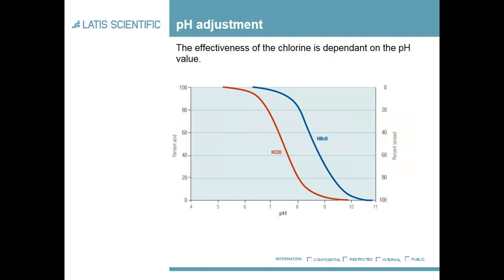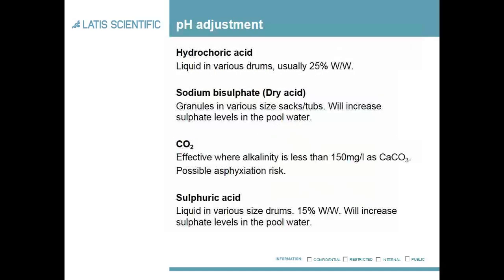Here you can see why pH is important for pools, because although you have a chlorine reserve in the pool, the effectiveness of that is dependent on the pH. The lower the pH you have, the more effective the disinfectant is. The ranges given earlier also reflect the fact that although a lower pH level is much more beneficial to the pool, unfortunately humans don't like very low pH or very high pH, so we have a comfortable range for humans to enjoy, as well as having an effective pool.